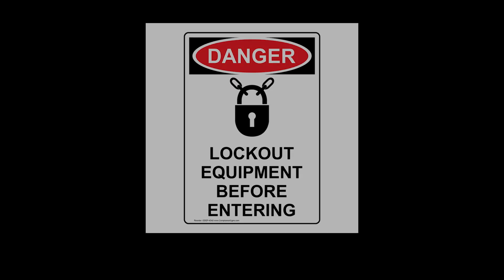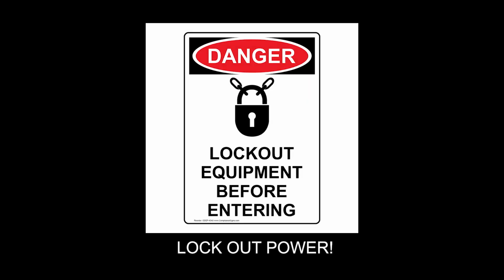The first step in setting up the Enduradrive ACS880 is ensuring proper wire connections are in place. Before you begin, it's critical that you lock out power. The permanent magnet motor generates potentially dangerous voltage whenever it spins. So for safety purposes, you must first isolate both incoming and outgoing power prior to exposing wiring. Always make sure you lock out the VFD power upstream of the device before exposing or altering any wiring.